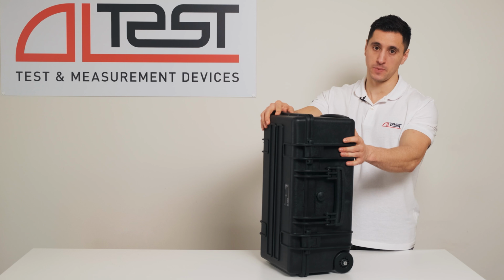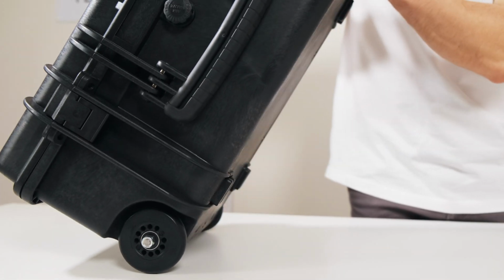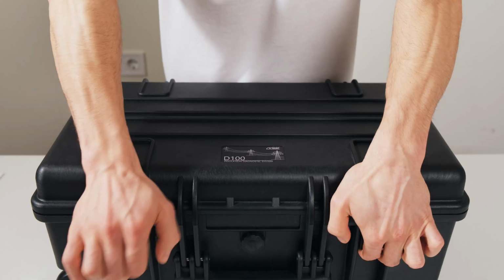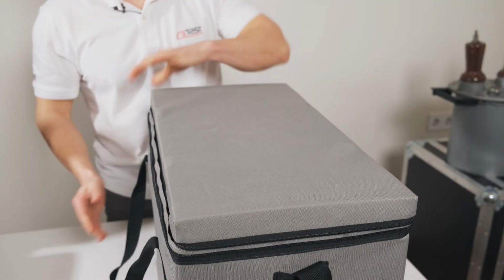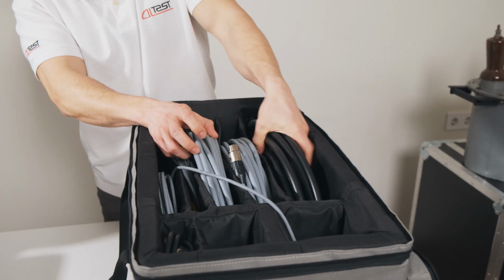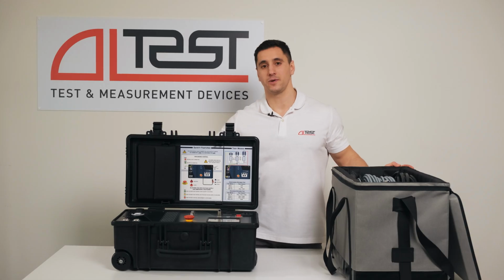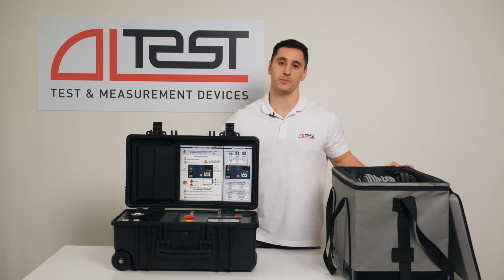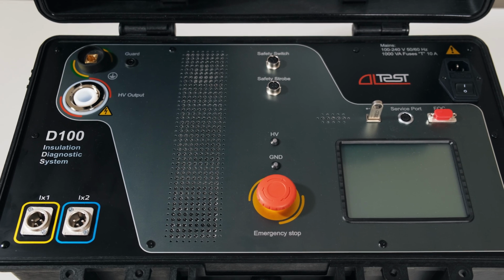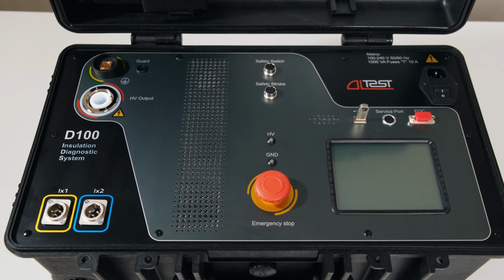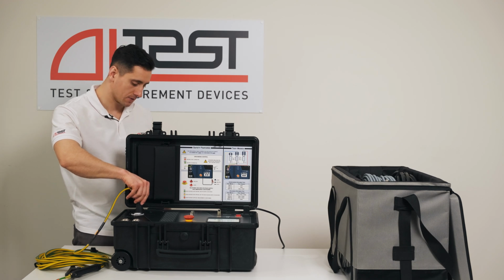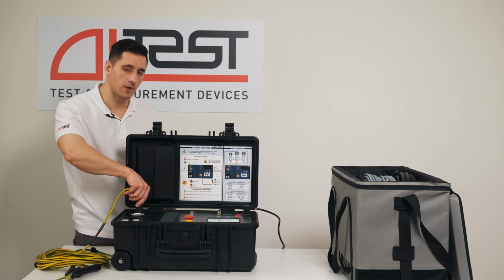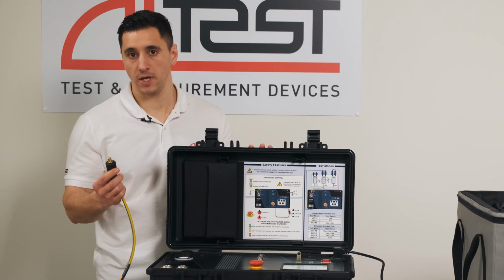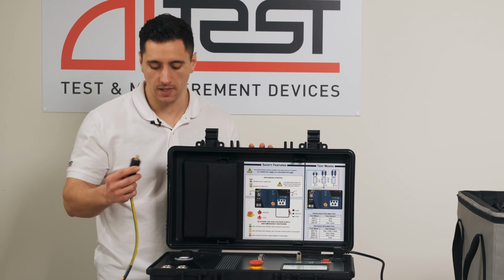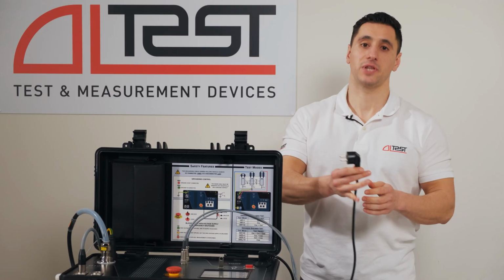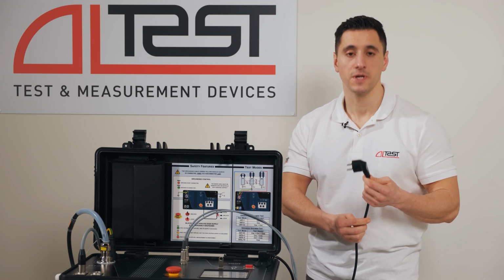The instrument is placed in a compact suitcase with wheels for convenient transportation. All the necessary cables are packed in an easy-to-carry bag. We prefer convenience, simplicity, and safety when working with the device. It has several levels of protection for maximum personnel safety. The high-voltage supply is locked if the grounding of the device is not connected correctly. The protective grounding cable must be connected to the grounding bus bar of the measuring object. The power cable must be connected to an outlet with a protective ground contact.